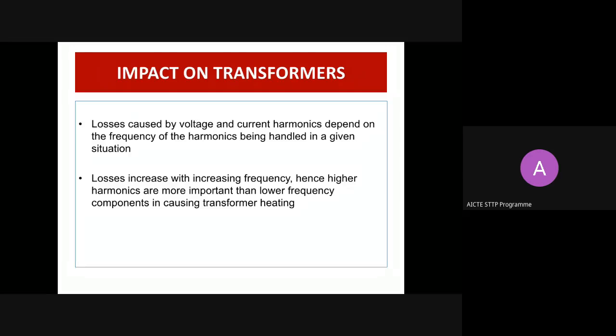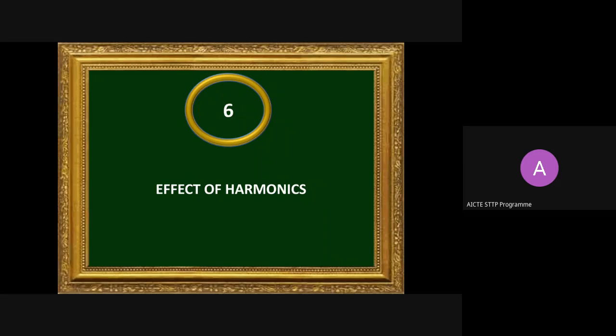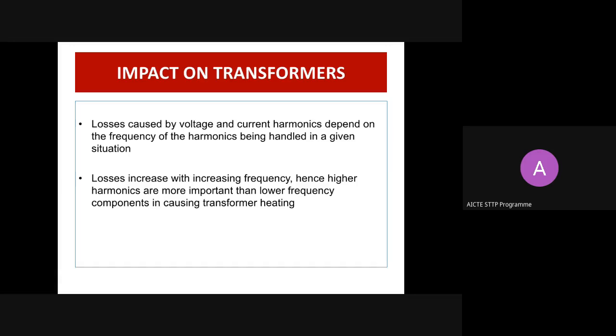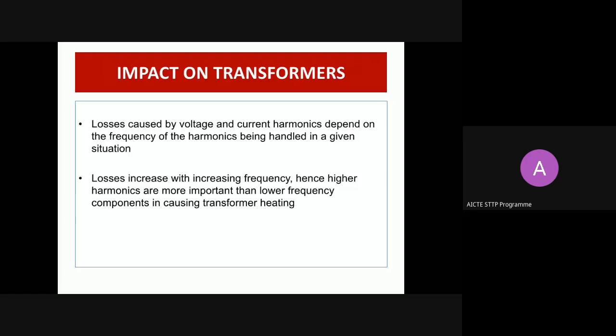Now we are going to think about the effect of harmonics. What is going to happen to the equipment present in the system? The basic prime equipment: transformers. With increasing frequency, with higher harmonics, naturally losses will increase. Losses caused by voltage and current harmonics depend on the frequency of the harmonics, in the sense of losses due to the fundamental frequency, the third harmonic, the fifth harmonic. If you think about it, when higher harmonic losses are very high, lower harmonic losses are very low. So we have to give more focus to controlling higher harmonic losses, since higher harmonics are more important than lower harmonic components in causing transformer heating.